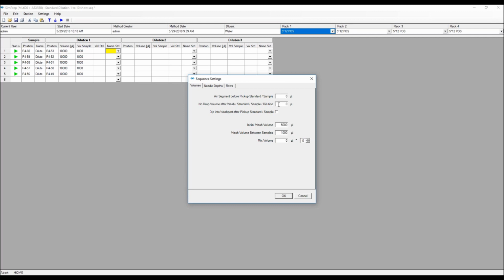The no drop volume after is more of a safety, just to make sure there's not any drips. It's a little less necessary, but it's a nice feature if that's something you're concerned about. The dip into wash port helps rinse off the outside of the probe. So between movements, it'll go back to the rinse port, dip in, just in case there's anything on the outside of the probe, to give it a chance to wash that off.